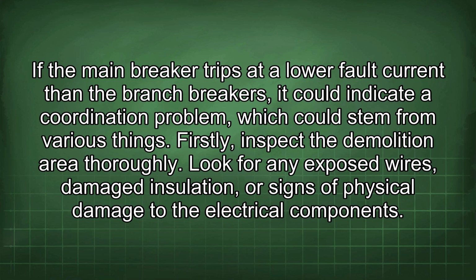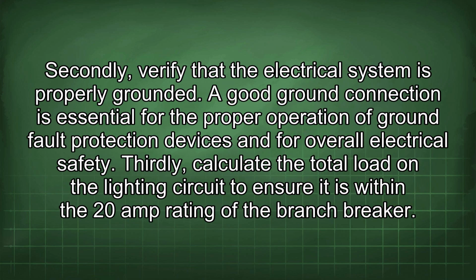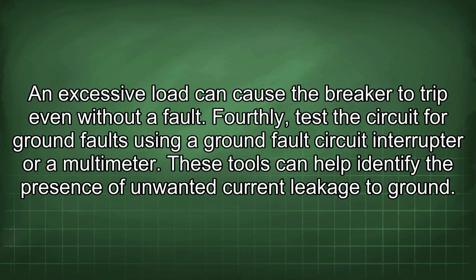Firstly, inspect the demolition area thoroughly. Look for any exposed wires, damaged insulation, or signs of physical damage to the electrical components. Secondly, verify that the electrical system is properly grounded. A good ground connection is essential for the proper operation of ground fault protection devices and for overall electrical safety. Thirdly, calculate the total load on a lighting circuit to ensure it is within the 20-amp rating of the branch breaker. An excessive load can cause the breaker to trip even without a fault. Fourthly, test the circuit for ground faults using a ground fault circuit interrupter or multimeter. These tools can help identify the presence of unwanted current leakage to ground.